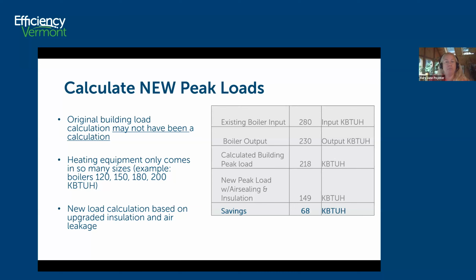And the calculated building load that I did, given that I had the footprint and I knew how it was constructed and I had done a pre-blower door test, we were able to come up with a peak load of 218. The other thing to consider is, if you have a peak load of 218, do you think a designer is going to pick a boiler for 220? Probably not, because they want to be sure that there's going to be enough capacity when it gets really cold. So in this case, the boiler output was 230. So it's not that bad of a match.